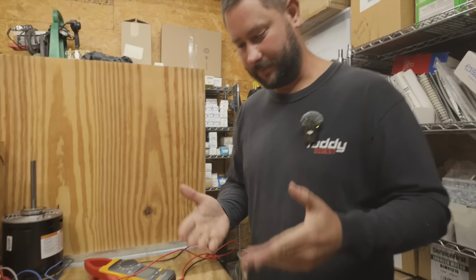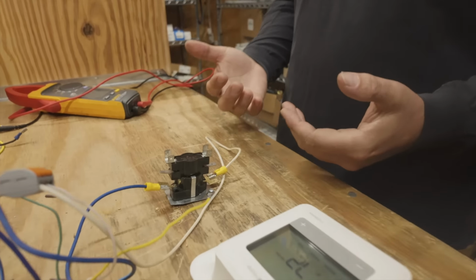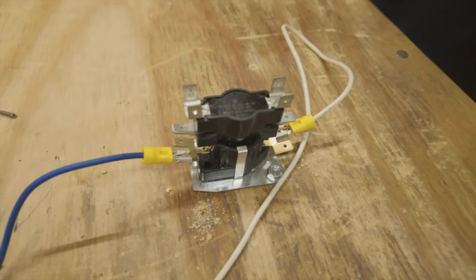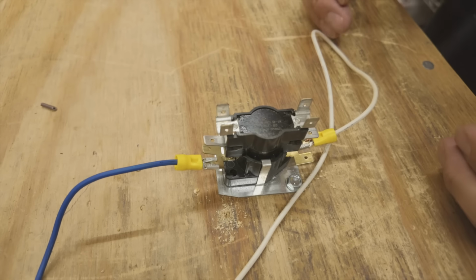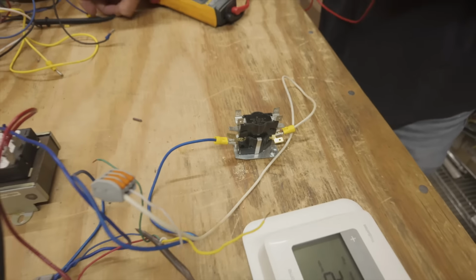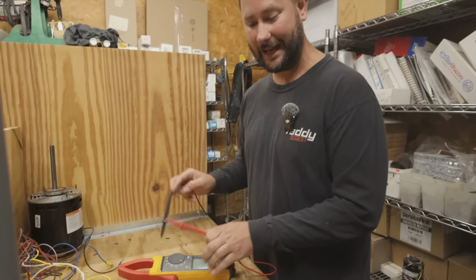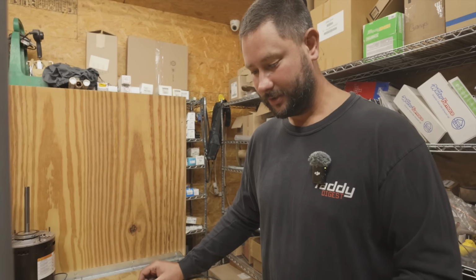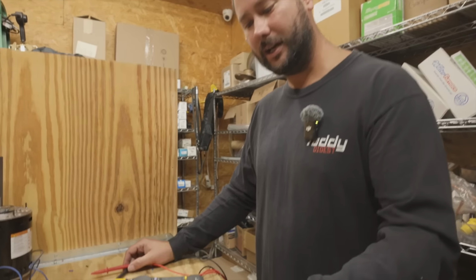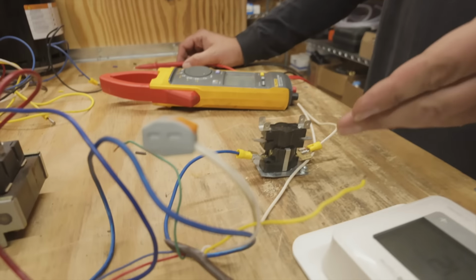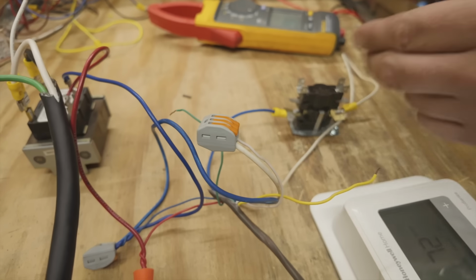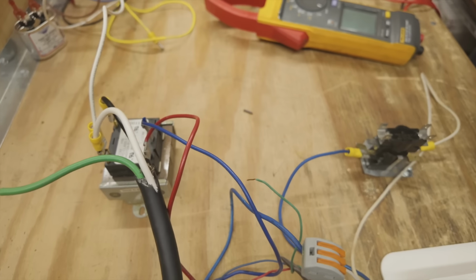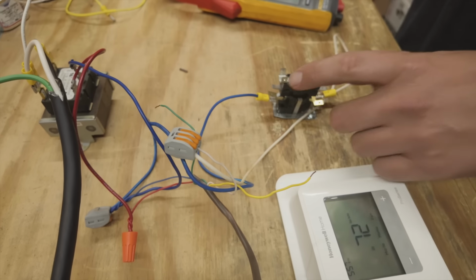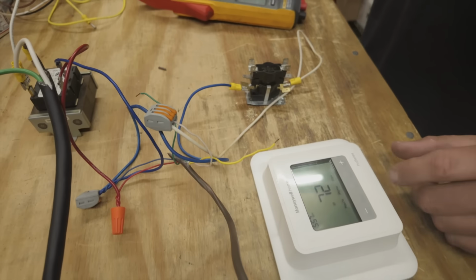Let's move forward. Next, we've got a sequencer, typically used in mobile homes and electric furnaces, to control a blower and to control a heating element. All right, let's go ahead and get our meter. We just got the coil hooked up. So we've got a white wire going to W on the thermostat. Typically, these are used for heating. And then we've got a common wire going to the common of the transformer. So we're providing the 24 volts whenever the thermostat calls for heat.